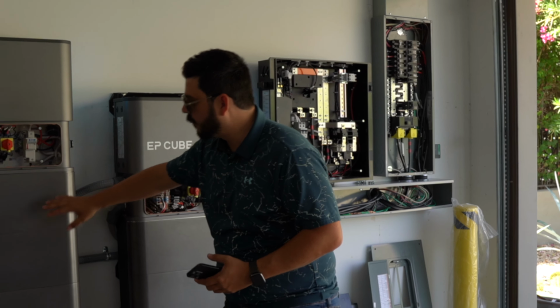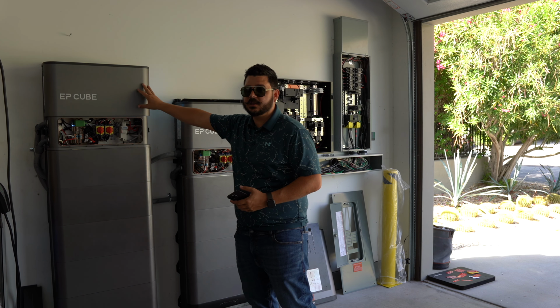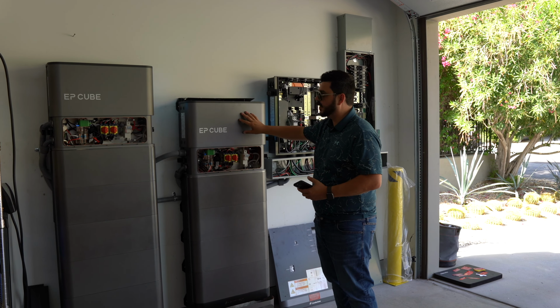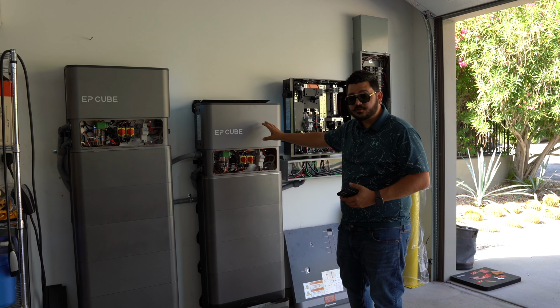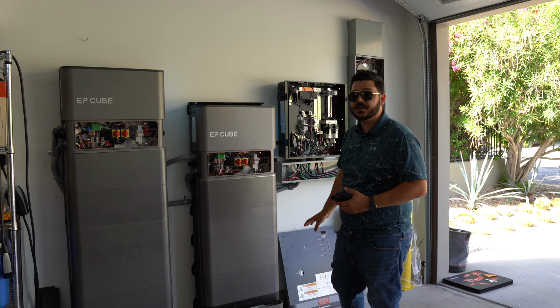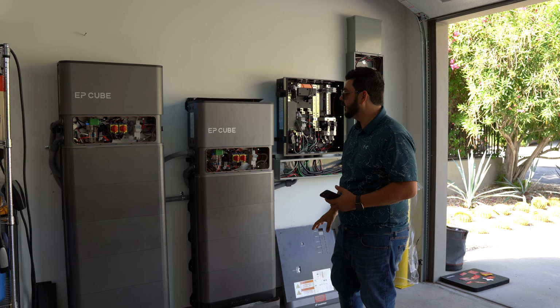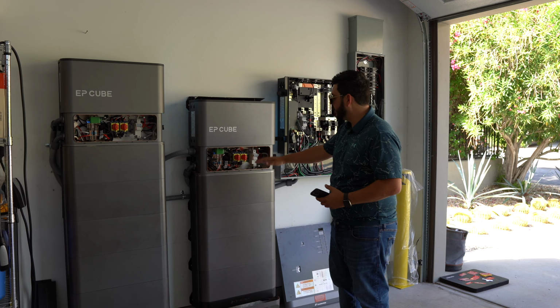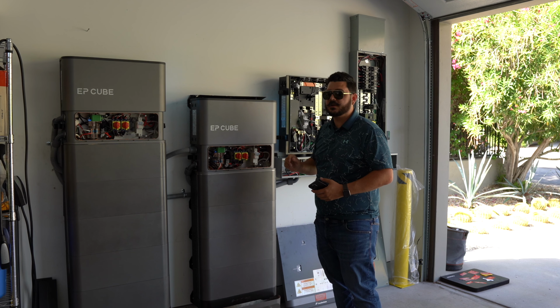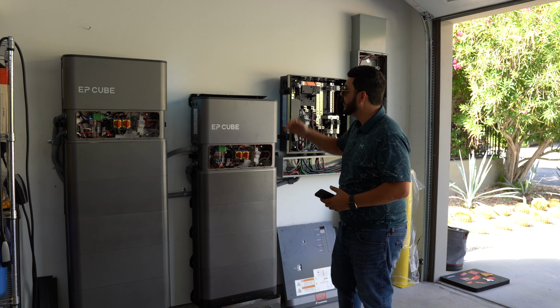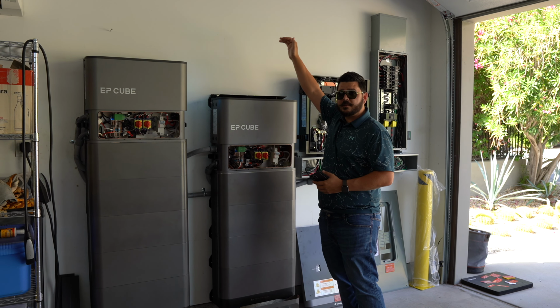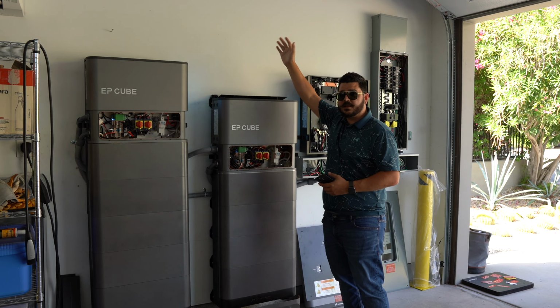So we can add one more battery module on this one to give us 20 kilowatt hours, and we can add two more battery modules on this one to give us another 20 kilowatt hours. So you can have up to 40 kilowatt hours of storage capacity just by adding a battery module. Yes, we have to remove the inverter, yes, we have to adjust some of the conduit, but the height, we're just going up, and there's no issues with that.